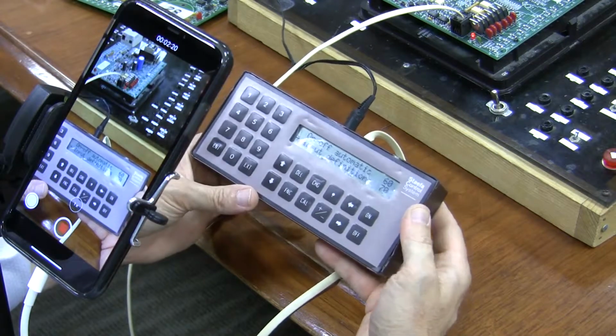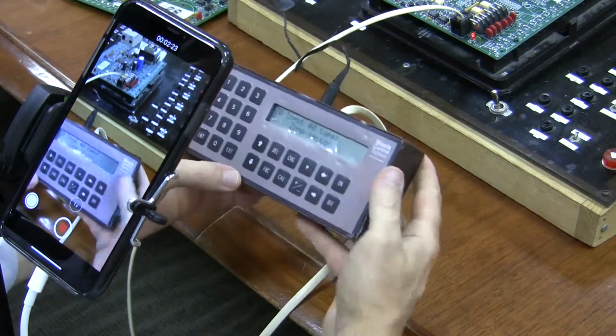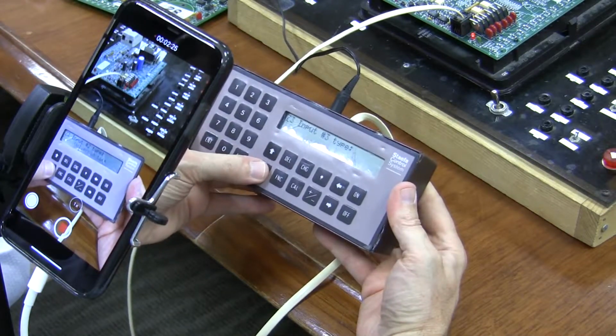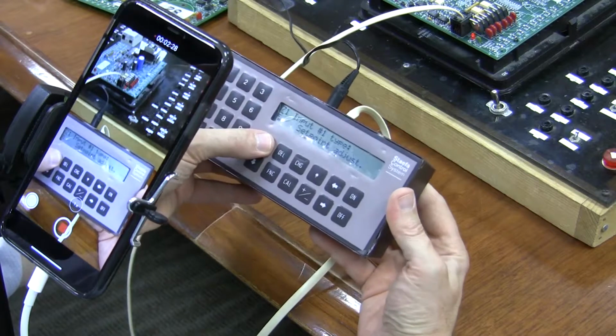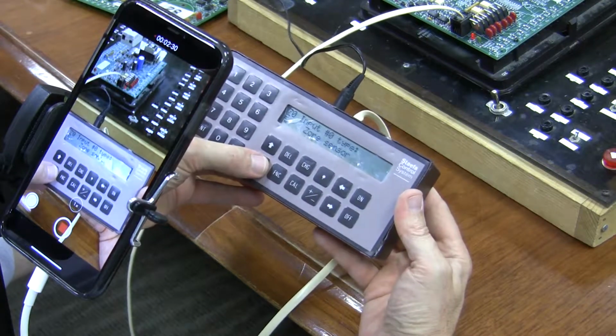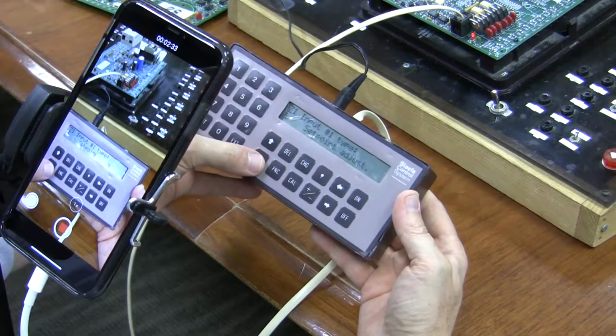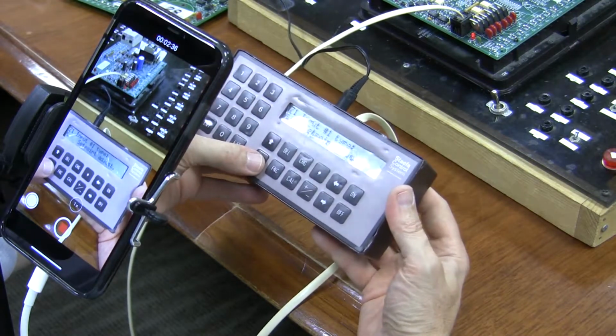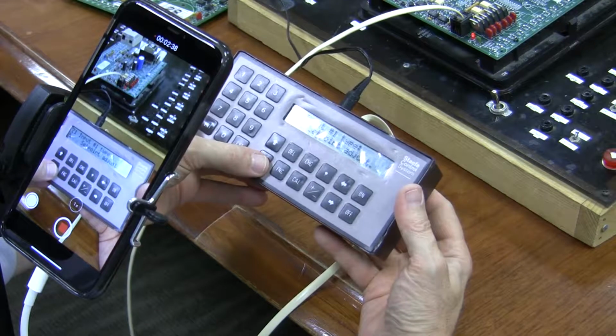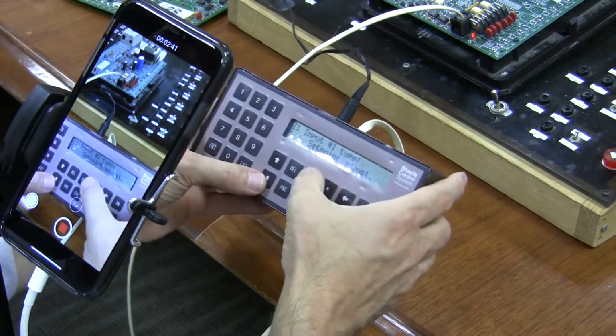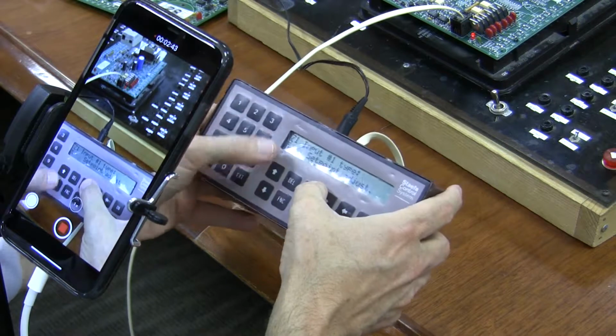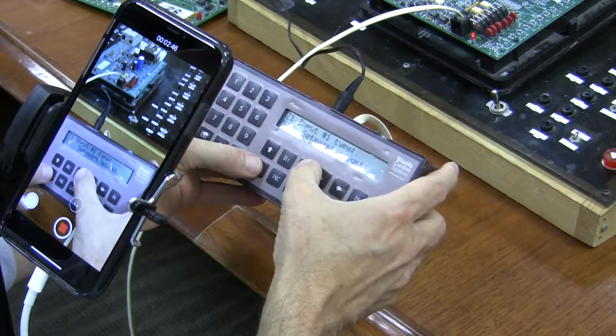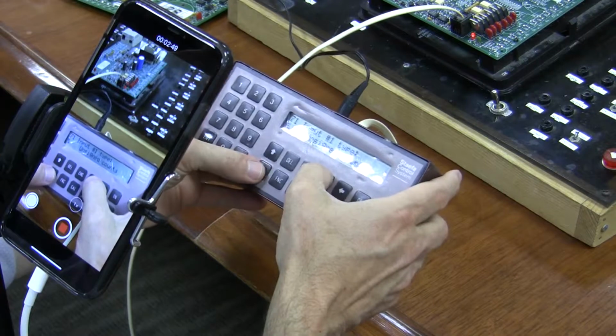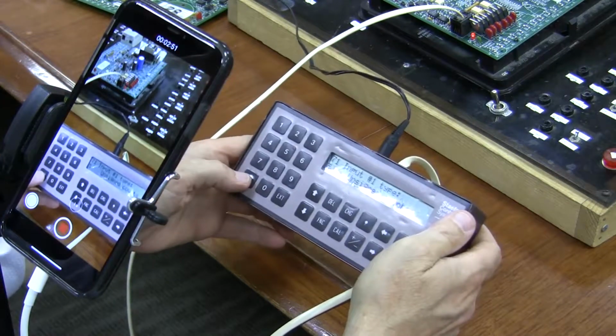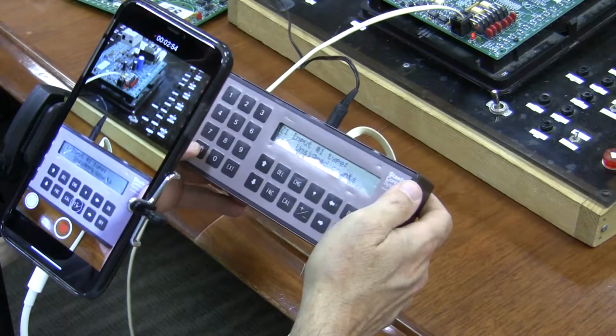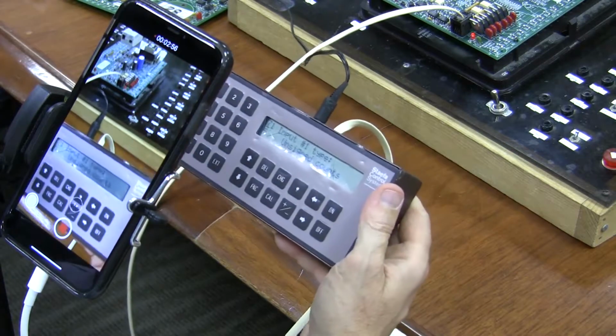So what I do here is I hit enter, and notice that now it's showing all the inputs, and it's telling me what it thinks is wired up to those inputs. So on input 0, it thinks it's a zone sensor. Input 1, it thinks it's set point adjust. So if I wanted to disable a set point adjust, for example, even though it's wired up, I could come here and I could go change, because I got the little CH there. Change. And now I could say unsigned counts, which is kind of it saying nothing. And I hit enter. And now I've basically told it that there's nothing wired up to the input.